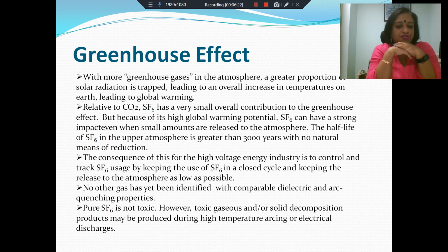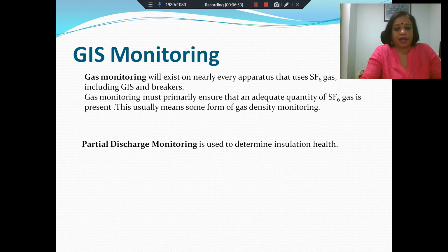But when you have discharges, or when the gas has been in operation for a long time, there might be a situation where the gas will decompose, and some of the byproducts of this gas can be toxic. They can result in toxic gaseous and/or solid decomposition products during high temperature or during electrical discharges, and that is a problem. So these are the safety issues that we need to keep in mind when we opt for GIS in lieu of AIS.